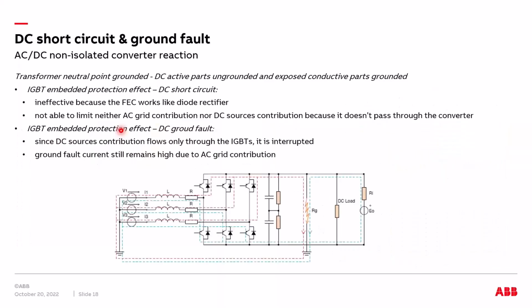If we consider the internal IGBT protection in case of a short circuit, it is totally ineffective because, as I said before, in case of a bolted DC short circuit, the currents pass through the freewheeling diodes. So even if we rely on the internal IGBT embedded protection, it is totally ineffective. So we are able neither to limit nor to interrupt both the AC grid contribution and the contribution coming from the DC sources.